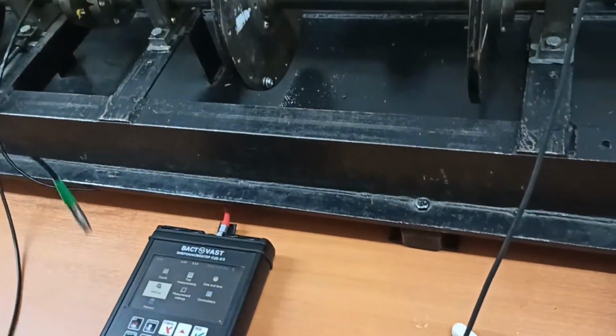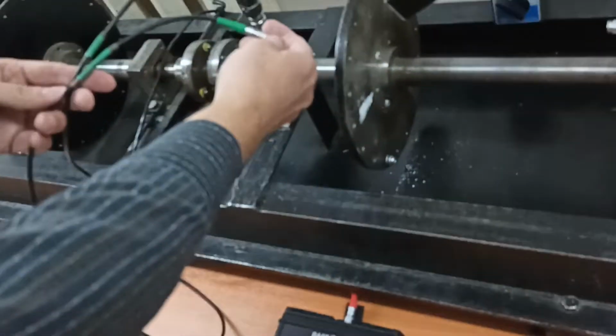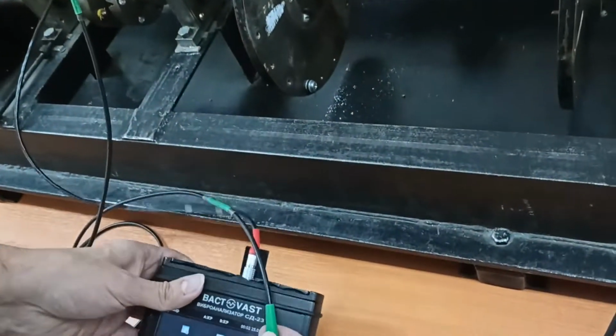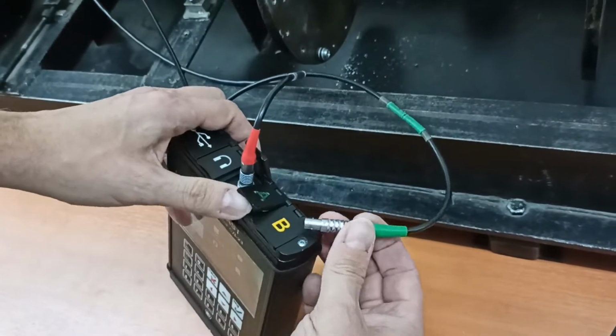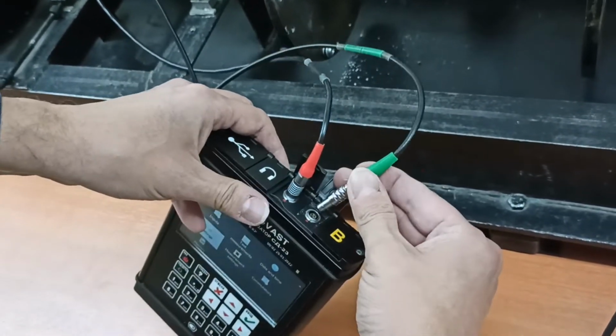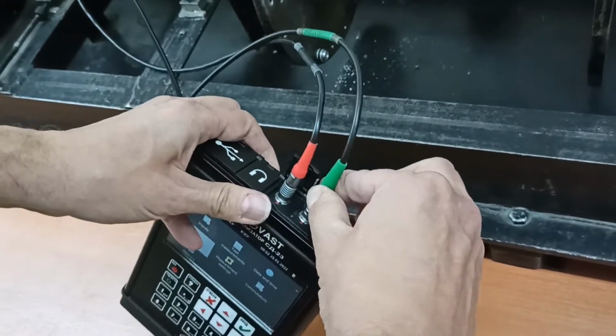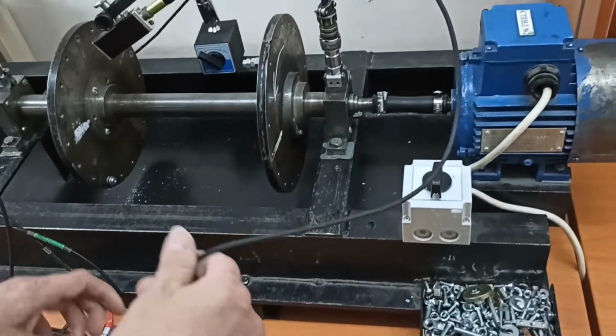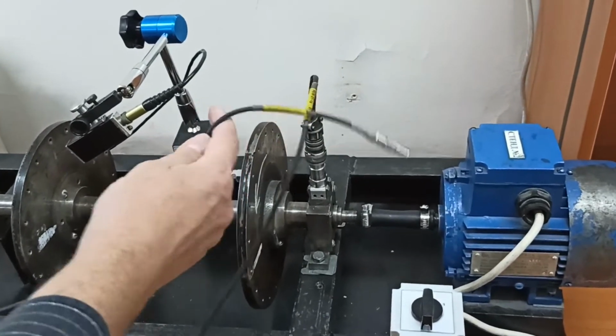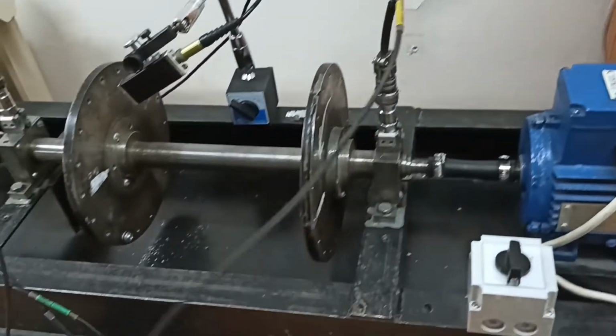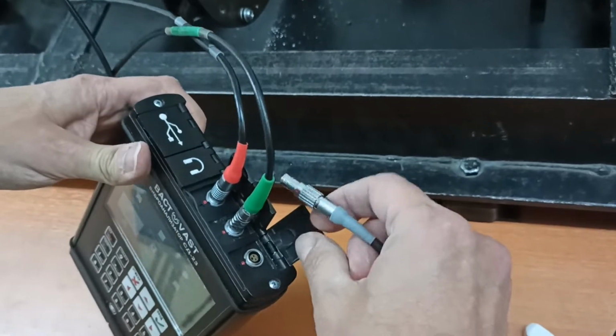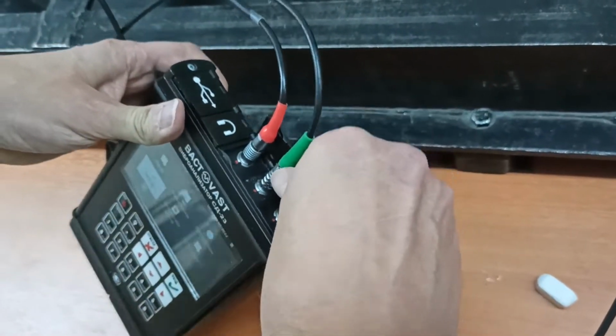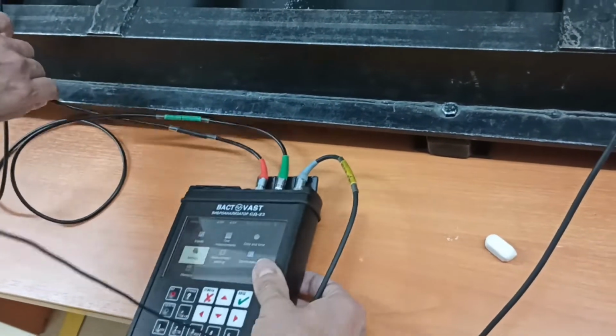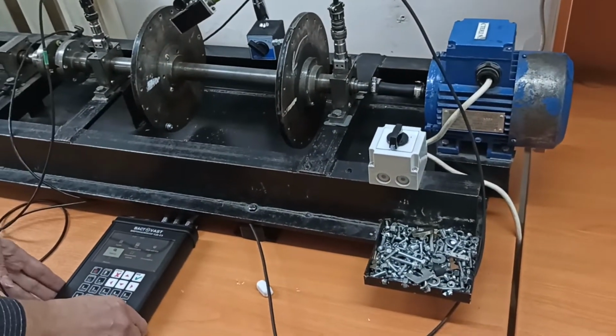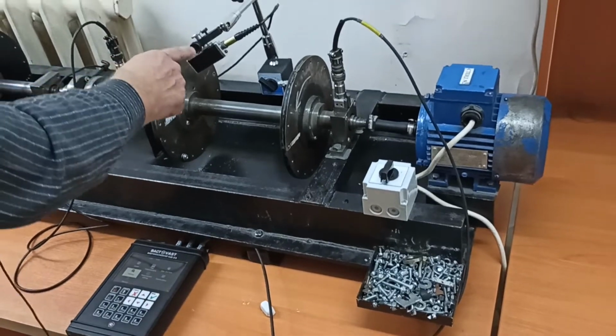Now we connect the sensors. One is the green sensor on both sides, green, and we connect it to the green channel. This will be channel A, or the first channel. Align the red dots and connect it. The second sensor is yellow, so we have yellow on both sides, and we connect it here, like this. Now the sensors are connected. We make sure the cables don't bother the rotation of our machine, and we will check the tacho probe.